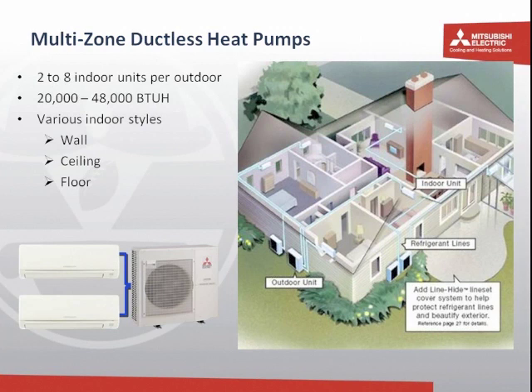In total, we make systems in the multi-zone configuration as large as 4 tons or 48,000 BTUs, so it expands a bit the overall capacity range that you'll get in a mini split system. And in addition to the traditional wall mount systems that are shown and that we looked at in the previous picture, the multi-zone brings in a collection of new style of indoor units, which are available in wall mount, ceiling mount, floor mount, and as I mentioned earlier, even a miniature ducted version that we'll be taking a look at. These could be mixed and matched in the space, so you could have a wall mount unit in one room, a ceiling mount in another, and a floor mount in yet a third.